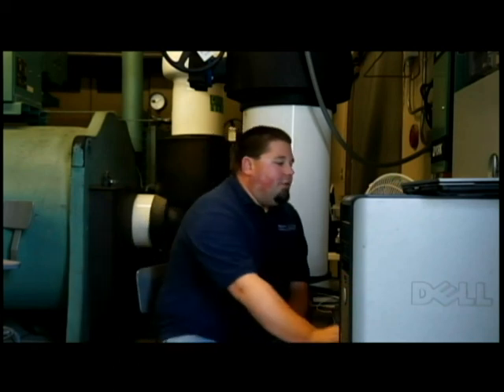So that covers how our plants start up, the basic sequence of how we get things running over here and how they operate. I wanted to show you as well, because I missed it. On the chilled water side, that outside air lockout is in the same mode request panel like it was on the hot water system. And currently the outside air lockout for the chilled water system is 66 degrees.